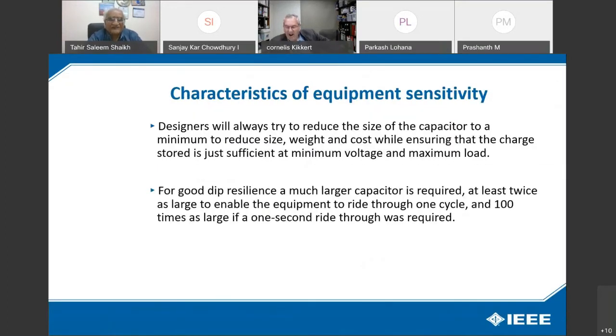Designers will always try to reduce the size of the capacitor to a minimum to reduce size, weight, and cost, while ensuring that the charge stored is just sufficient at minimum voltage and maximum load. For good dip resilience, a much larger capacitor is required, at least twice as large to enable the equipment to ride through one cycle, and 100 times as large if 1 second ride through was required.